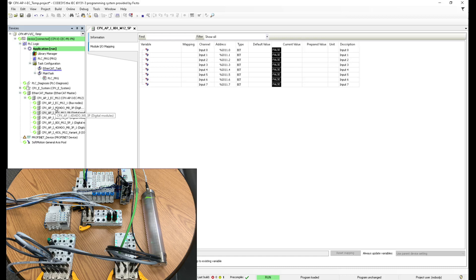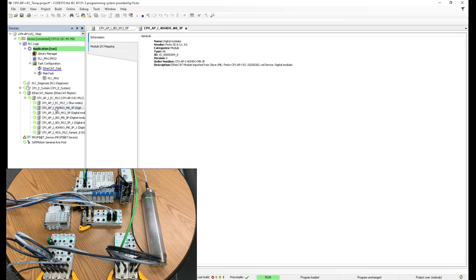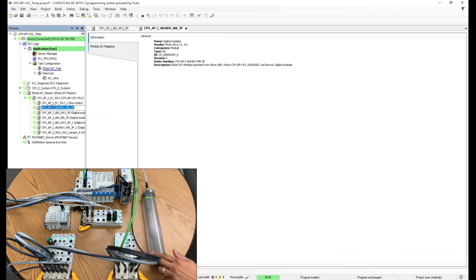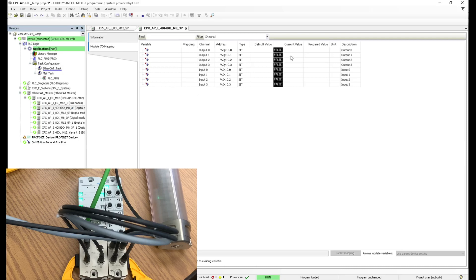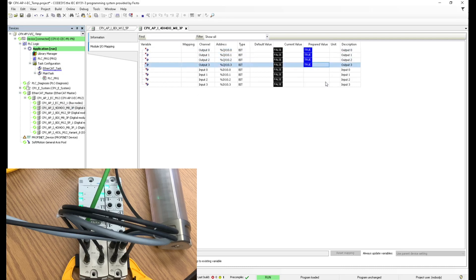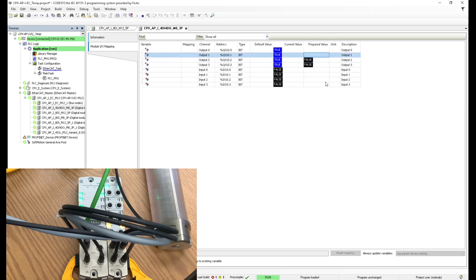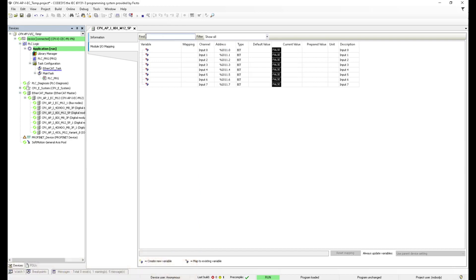I could also test my outputs. So let's do that. I'm going to select this module, which is this one over here, and I'm going to go to IO mapping and I'm going to set those outputs to true. You can see them switching on to true. Awesome. So I have some communication there.